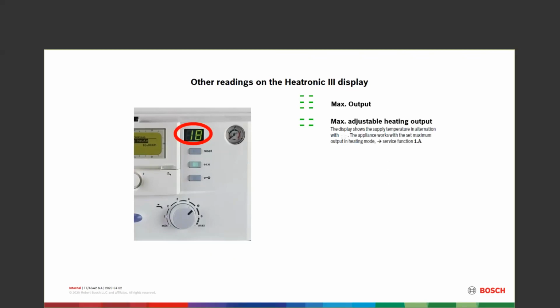We look at service function 1A. We can look at what that set max is, and we can change that. I'll go into that a little bit. Minimum output is low fire, and that locks that burner down for 30 minutes into low fire. L is thermal disinfection, and we can set that on heat only so that we can actually increase on a timed basis the temperature of the tank to disinfect thermally any possibility of bacteria in there. It's going to bring that tank up to about 158 degrees, maybe even a little bit higher than that. Get you well above the 140 that will kill Legionella and other bacteria in there. So it can be programmed in to do it on a periodic basis.